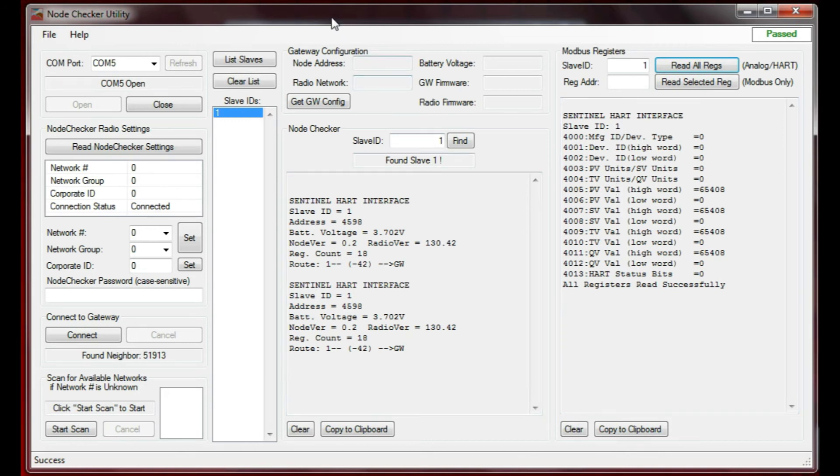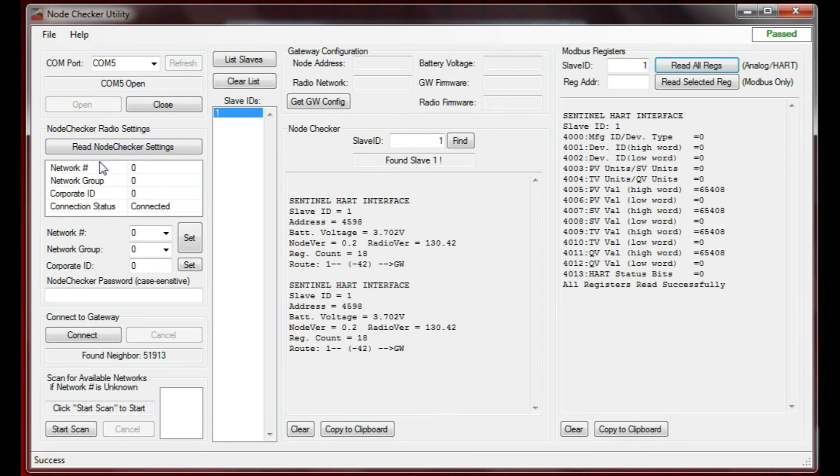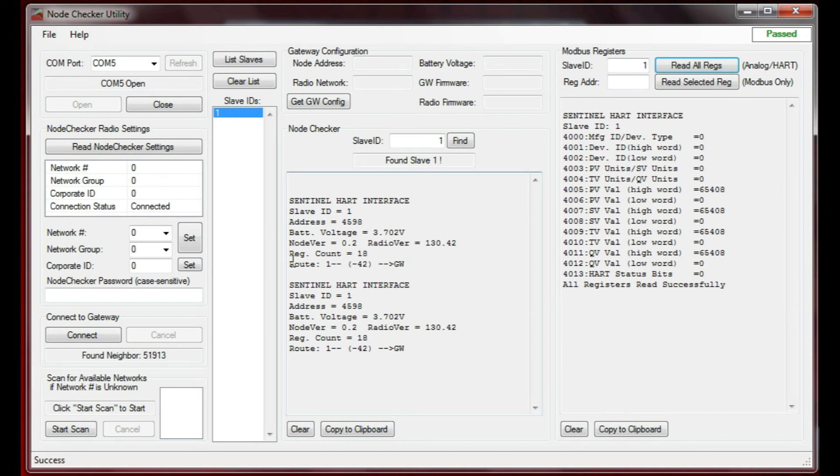That's the node checker utility. Its real strength is if you're out in the field installing a node and you want to know if it's connected correctly. Without going back to the gateway, you can set up your node checker, connect to the gateway with the right network group and corporate ID, add a password if you need it, connect to the gateway, list the slaves, and double-clicking on individual slaves will give you information on them. That's what you need to know that the system is connected correctly.